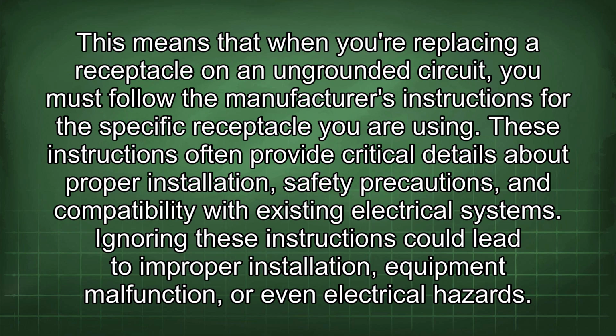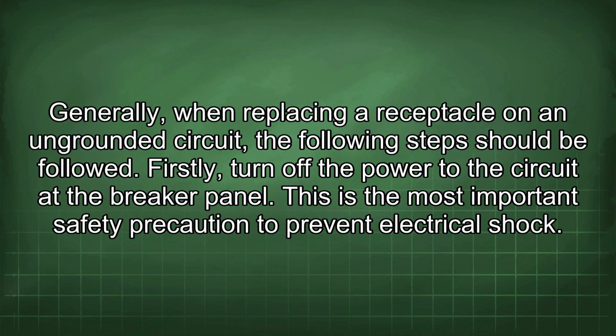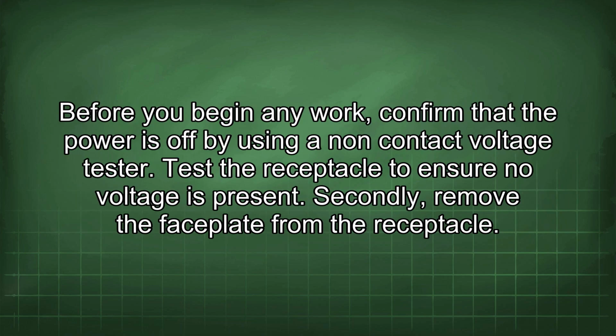These instructions often provide critical details about proper installation, safety precautions, and compatibility with existing electrical systems. Ignoring these instructions could lead to improper installation, equipment malfunction, or even electrical hazards. Generally, when replacing a receptacle on an ungrounded circuit, the following steps should be followed. Firstly, turn off the power to the circuit at the breaker panel. This is the most important safety precaution to prevent electrical shock. Before you begin any work, confirm that the power is off by using a non-contact voltage tester. Test the receptacle to ensure no voltage is present.